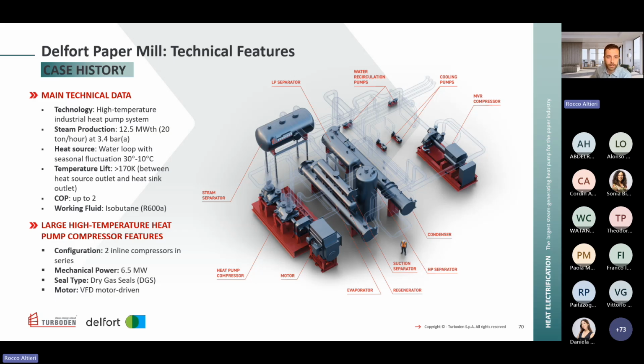On the left, high side, let's say, of the picture, you see the steam separator, basically the steam generator that is feeding the MVR compressor. So this is the plant. It was quite a challenging project because the plant has to be inside a building that was already present on site. So we had to manage the layout in a way that everything was fitting the rooms available.